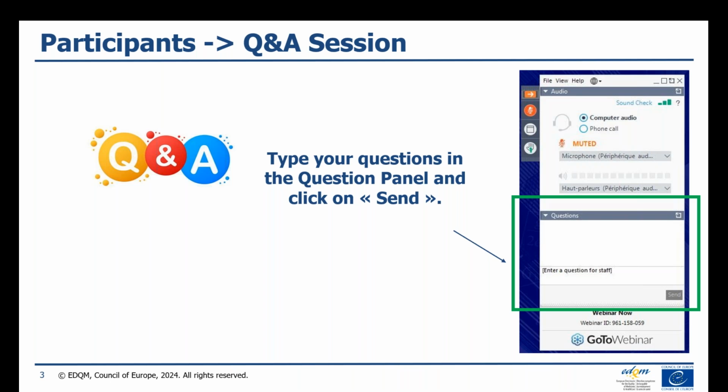I see a new question popping in. Why don't we provide the uncertainty? This is because, as I said before, and as Marilyn said as well, we only provide data which is needed for the use of the CRS as it is intended. Because the specifications set in the monograph already take into account the uncertainty of the reference standard, and we assure that the uncertainty of follow-up batches is negligible to these specifications, you don't need the uncertainty to perform the test as it is described in the monograph. Right.